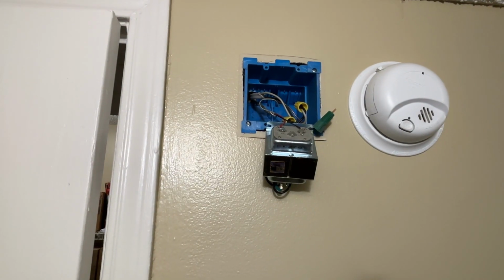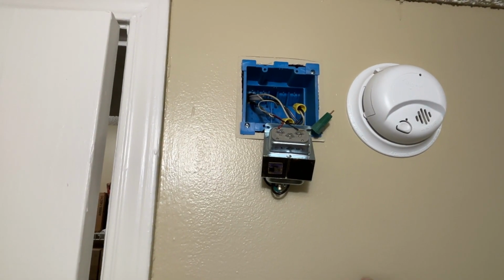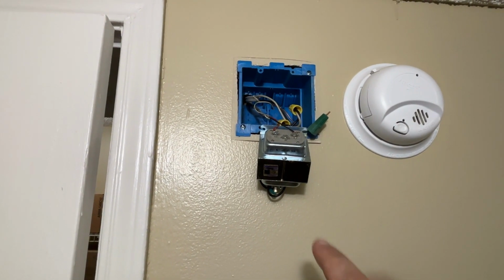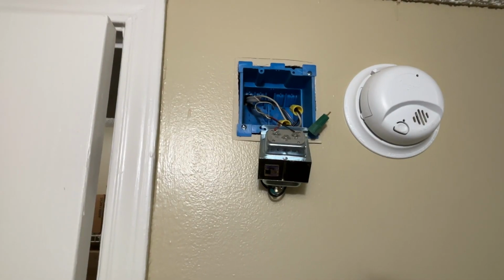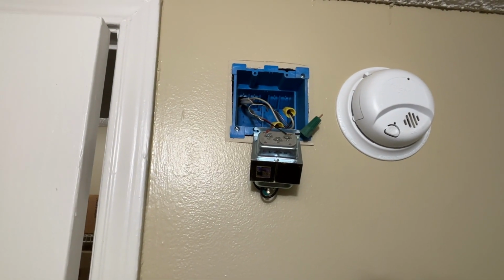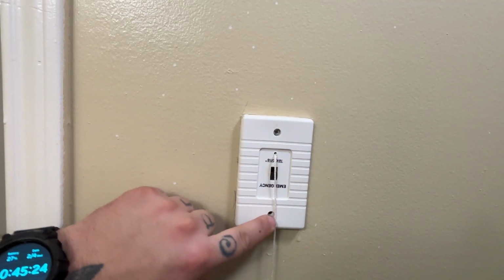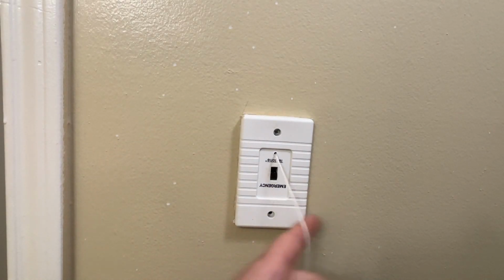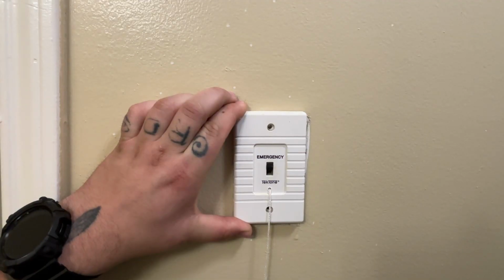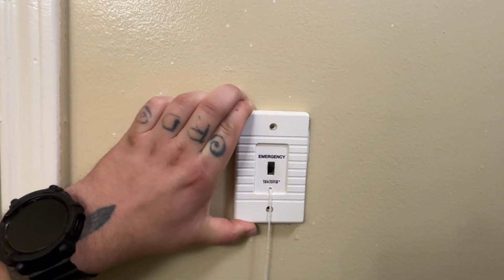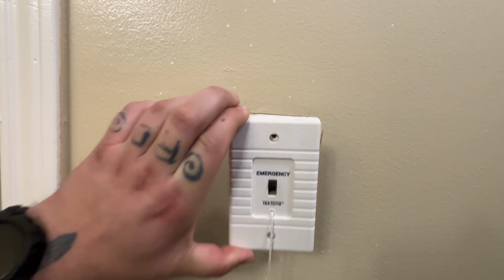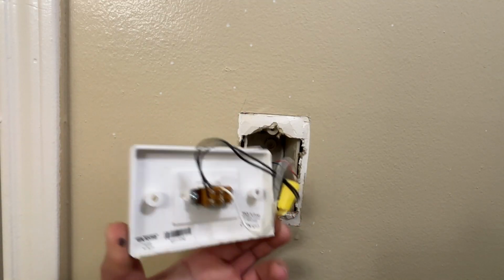The switch activated, if you are not getting a voltage drop at your transformer, then we will go and troubleshoot the switch. Removing the two screws and remembering to score around this so we do not bring the paint with us, we can remove this faceplate. With our faceplate now turned the right way, and the screws removed, we can remove this, exposing our wires in the back of our switch.